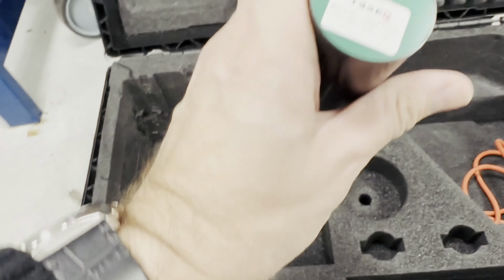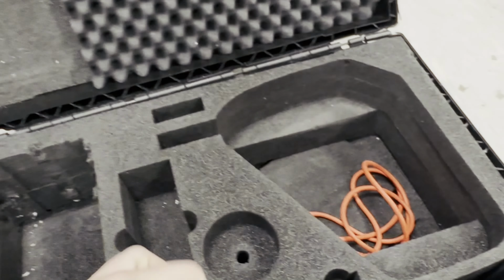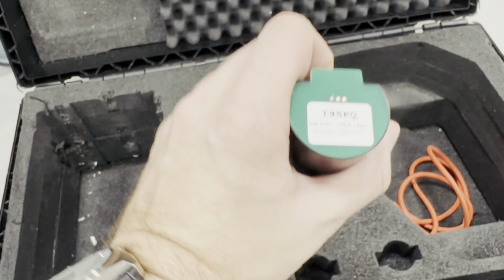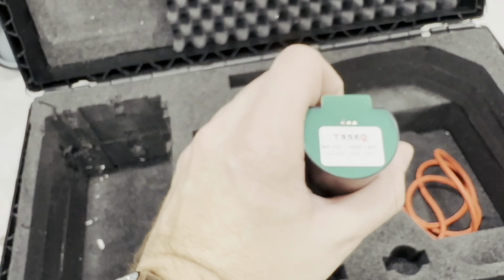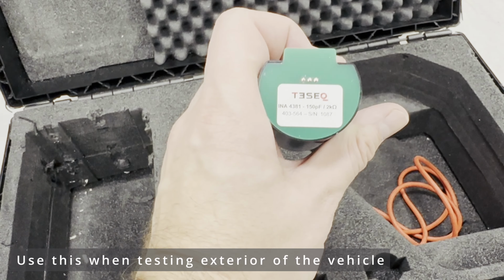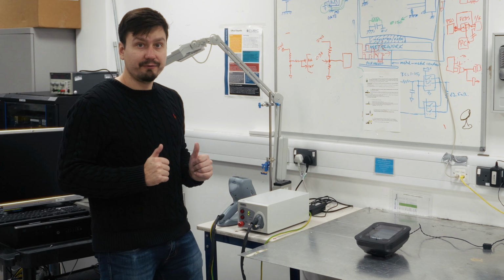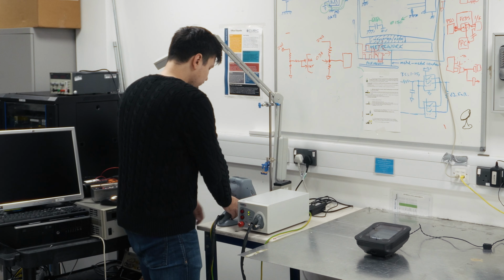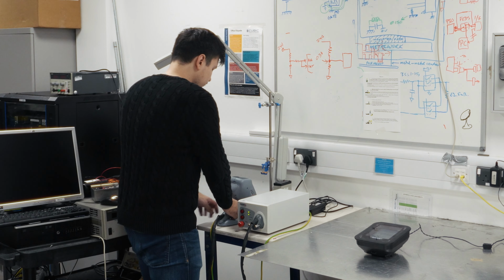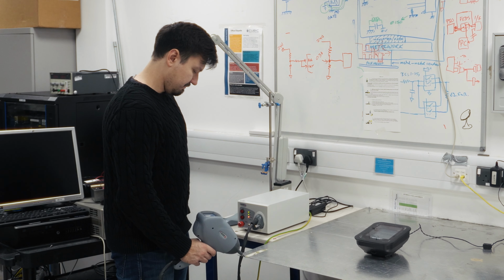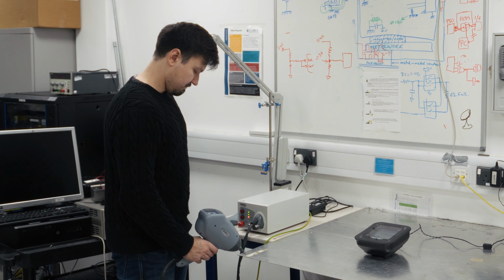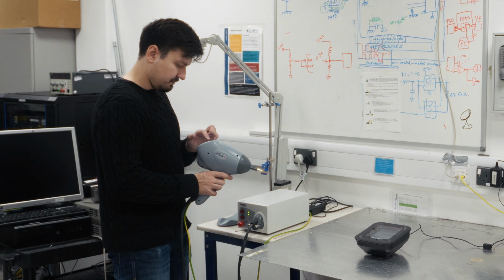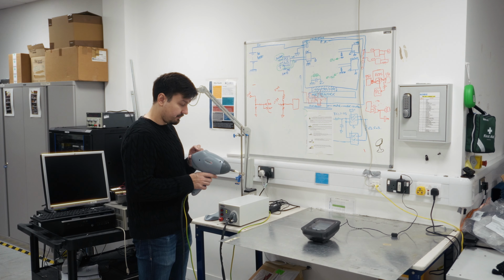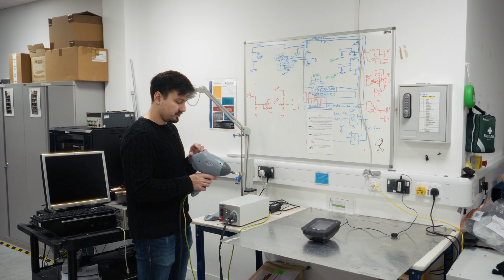Now, as I was saying, there are several other options available. So this is the network module with a 2 kilo ohm tip resistance, and this is the network module with 150 picofarad tip capacitance and 2 kilo ohm tip resistance. Now we are finally ready and we can begin the test. The first thing to do is to apply the contact discharge into the coupling plane to check that it works. Okay. We can also adjust the settings of how we apply the discharge. For example, I like to use press to start and release to stop.